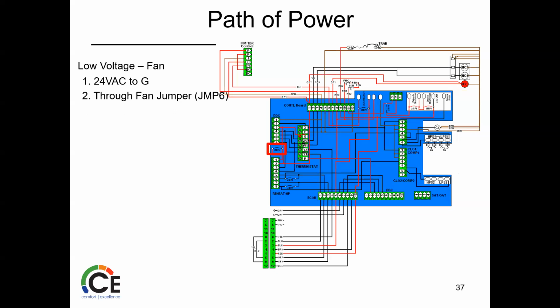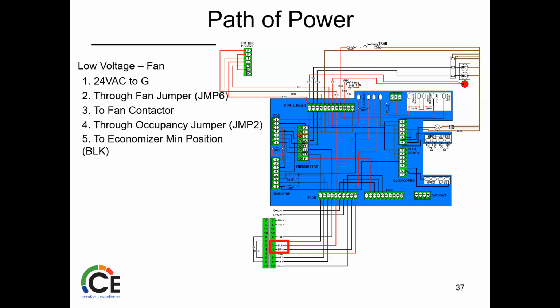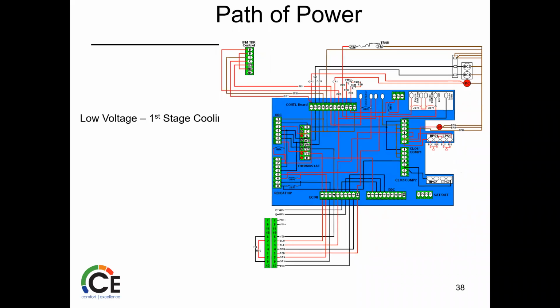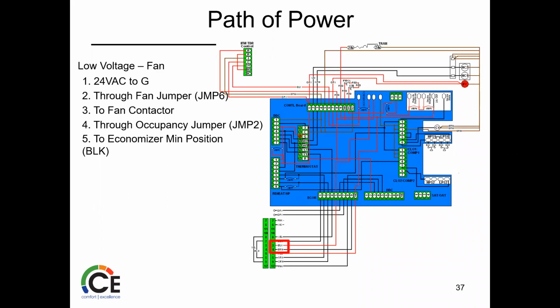So obviously if that's intact, then it's going to hit the indoor fan contactor. And then again, it's going to start looking, make sure occupancy is not used if there's a jumper there. And then we're going to look down here, depending on if there's an economizer. No economizer, no big deal, and then off it goes. If you have it, obviously then it's going to send that to minimum position, because we're running the fan, right? But if you don't, then it just dies there and the fan runs.